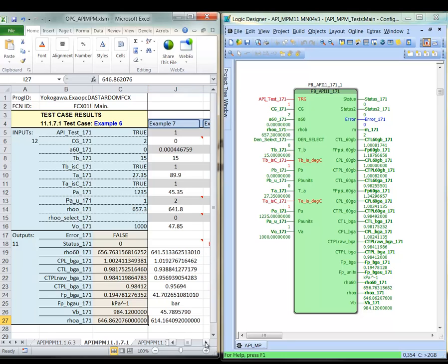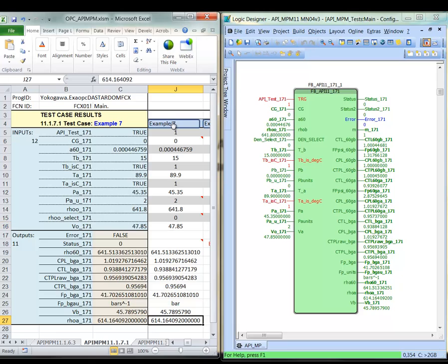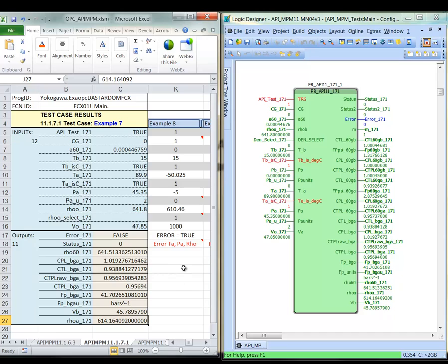Of course, we use these algorithms to generate net oil computations and water cut computations for flow calculations, correcting flow calculations in a net oil computer in hydrocarbon custody transfer situations. These can actually be applied to non-petroleum applications as well, but then some modifications would have to be done in terms of the algorithms, in terms of handling the density of that kind of fluid. These API MPM calculations are actually designed specifically for crude oil, refined oil, and lubricating oil. That concludes the test for 11.1.7.1.